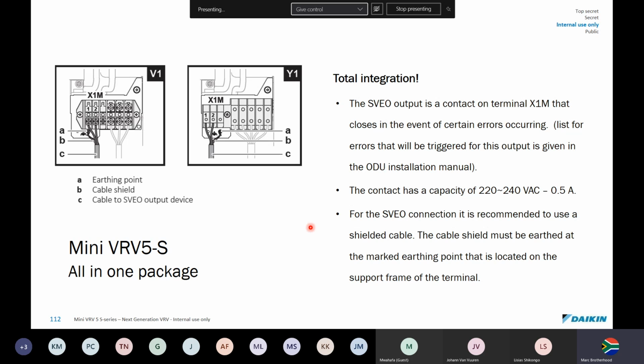For the SVEO connection, it's recommended to use shielded cable. The shielded cable must be earthed, and whenever you earth a shielded cable, you only earth the one end. On the units where you plug it in, you can generally leave that earth off. What it does is prevent what we call capacitive coupling, and it just makes sure the voltages are true. That being said, this is a higher voltage, but on the lower voltage stuff, your F1, F2s, you don't ever earth both ends. You don't earth the VRV outdoor, then go all the way and earth the furthest VRV indoor unit. That's not going to work.